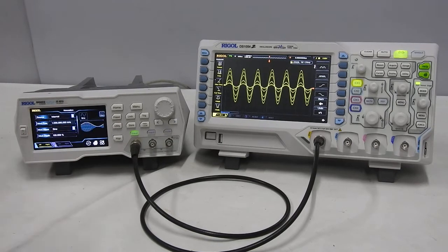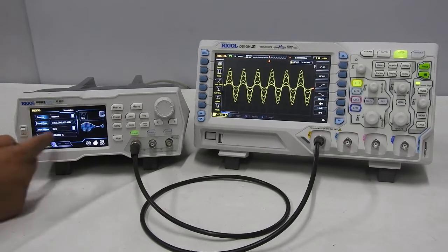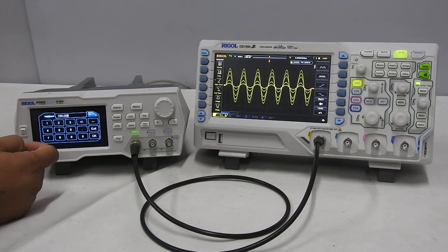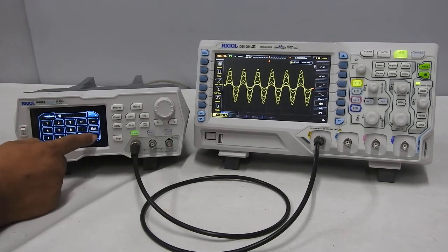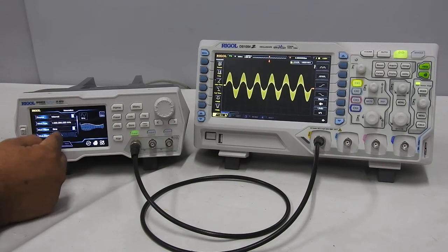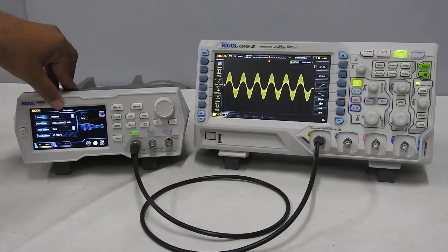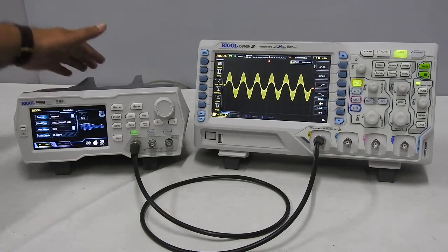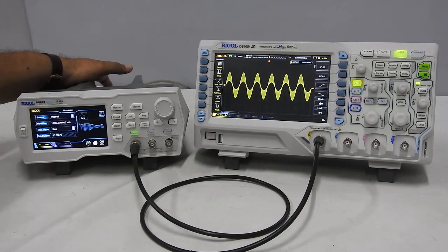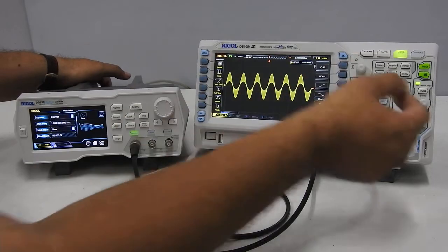Okay, this is the modulating frequency. What should be the modulation depth? I can select modulation depth from here. Let's say 50%. So I have selected the 50% modulation index. The source is internal, whether you have internal modulation or external. External I can connect from the back side, there is a BNC, I can connect an external signal from there.